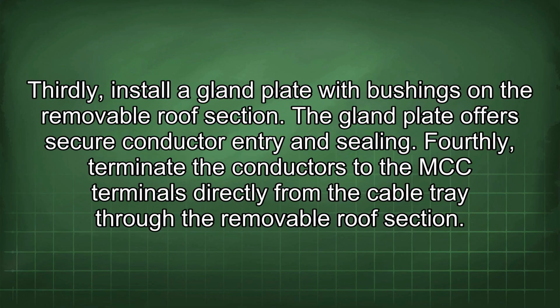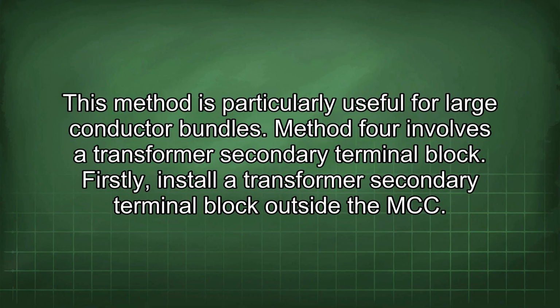Thirdly, install a gland plate with bushings on the removable roof section. The gland plate offers secure conductor entry and sealing. Fourthly, terminate the conductors to the MCC terminals directly from the cable tray through the removable roof section. This method is particularly useful for large conductor bundles.